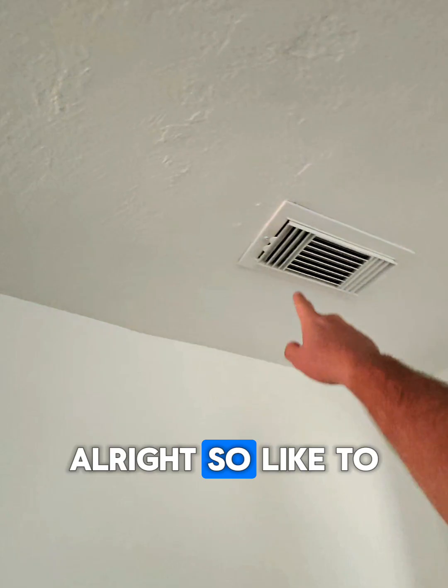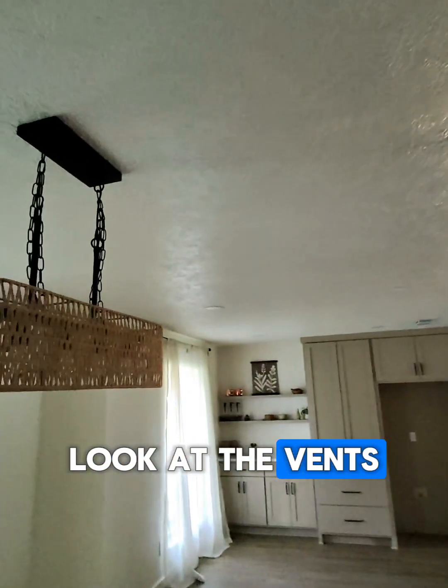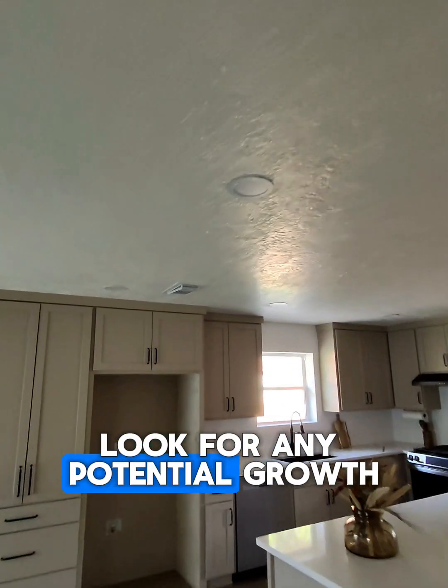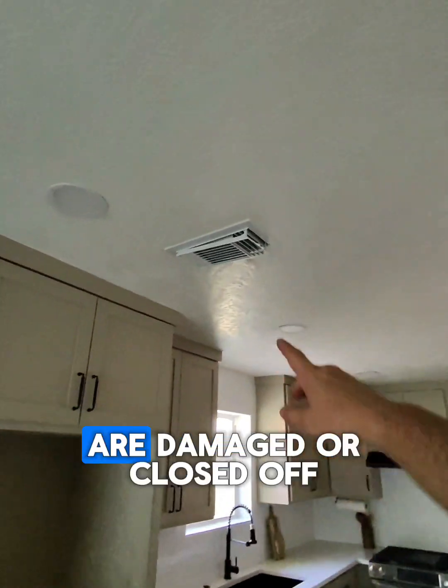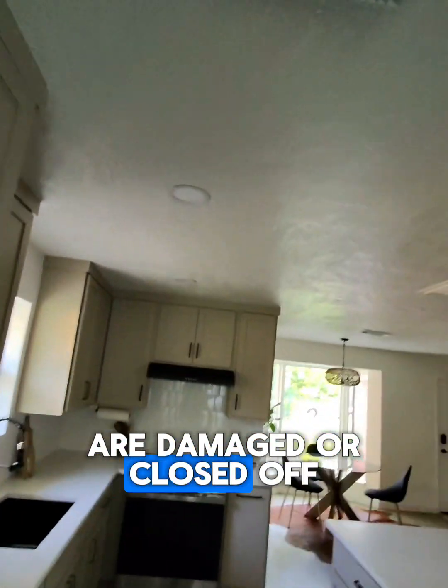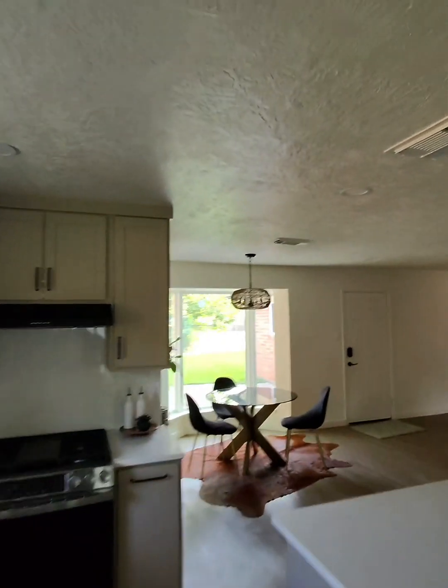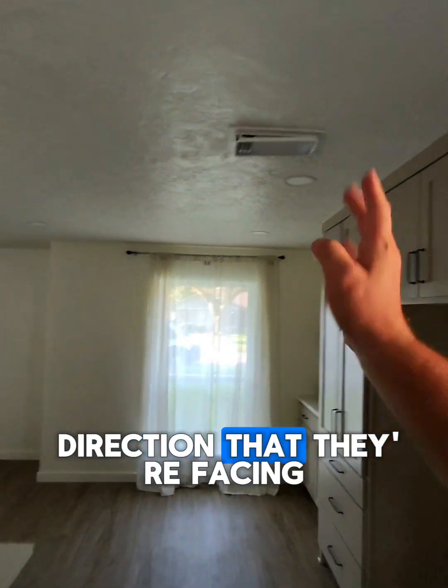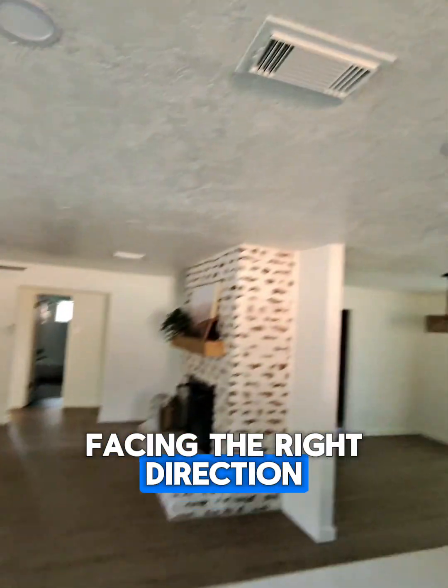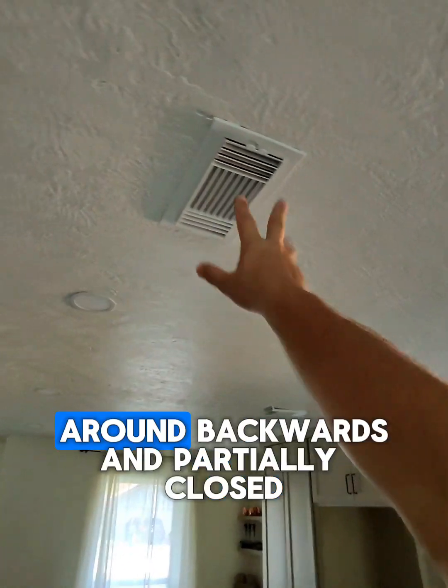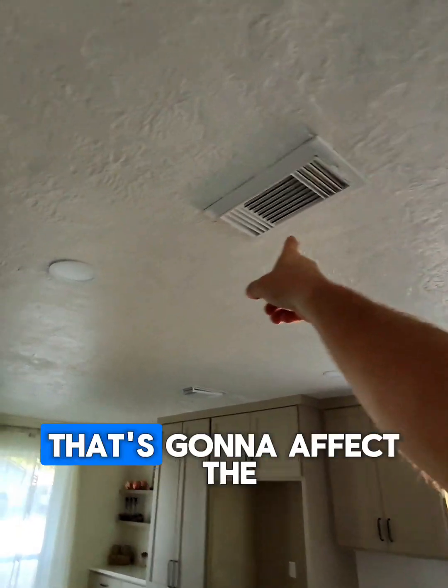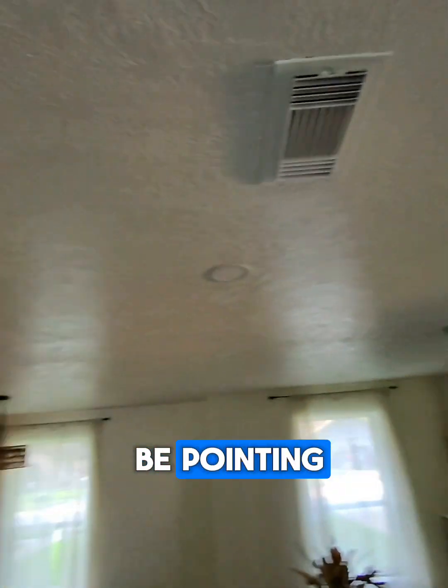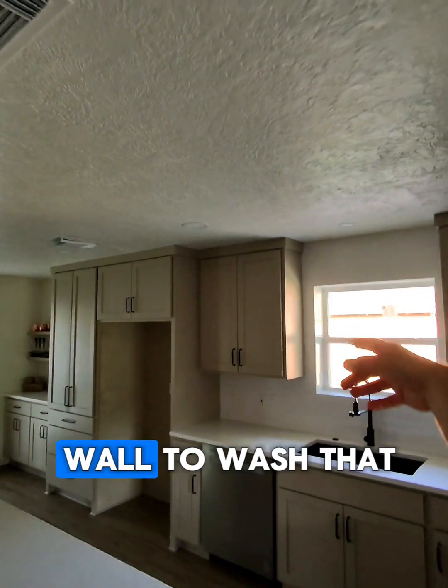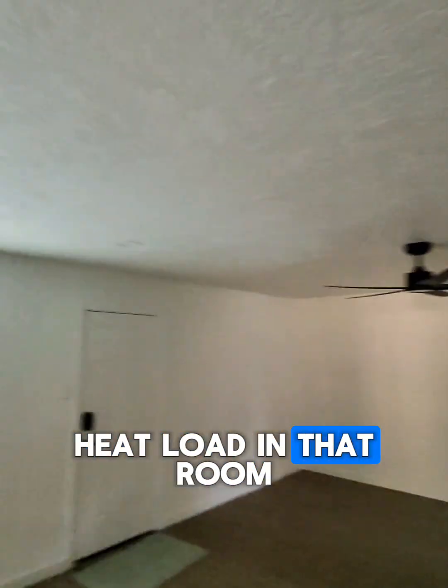Alright, so I like to come in, look at the vents, look for any potential growth or any vents that are damaged or closed off. Also look at the direction that they're facing, make sure that they're facing the right direction to get the best heat load. Like this one's swapped around backwards and partially closed. That's going to affect the airflow, and then it should be pointing usually towards an exterior wall to wash that heat load in that room.